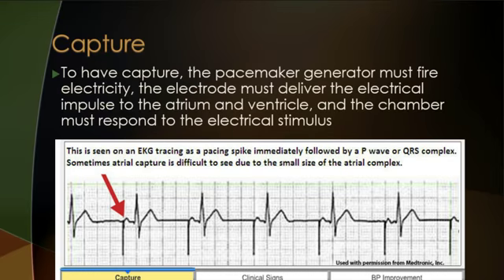So what does having capture mean? Well, for capture, the pacemaker generator has to fire electricity. The electrode must deliver the electrical impulse to the atrium and the ventricle, and the chamber must respond to the electrical stimulus. So capture is seen on the EKG tracing as a spike immediately followed either by a P wave or a QRS complex, depending on which chamber you're trying to pace. If you're trying to pace your atrium, then you want to see the spike before the P wave. If you're trying to pace your ventricles, you want to see the spike before the QRS complex. And if you're trying to pace both chambers, you should see a spike before your P wave and a spike before your QRS complex.